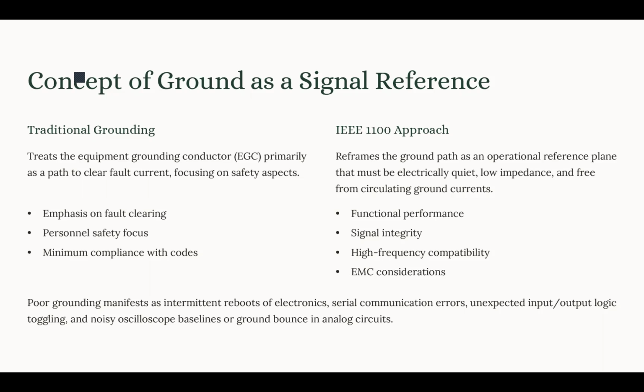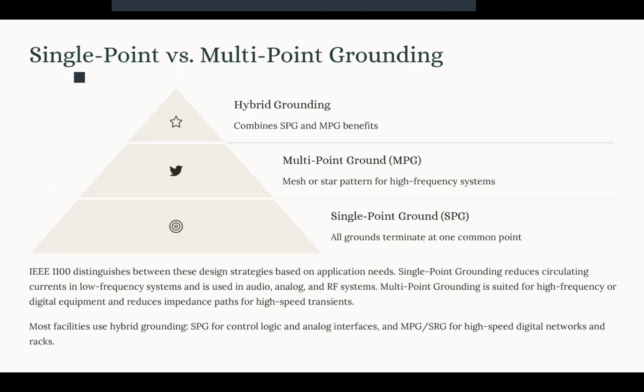Now, if we do not have a good signal reference grounding, there are some consequences. One would be a manifestation in the sensitive electronic equipment, for example, unexpected logic toggling and analog noise in our system. As we mentioned, we have different grounding strategies. But why do we have that? This is because we want to provide a stable, low noise reference plane for those sensitive electronic equipment, while meeting the safety and EMC requirements.